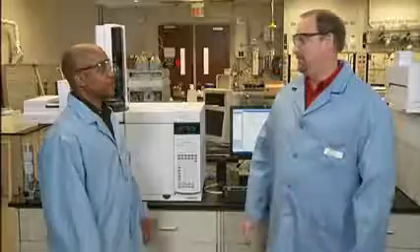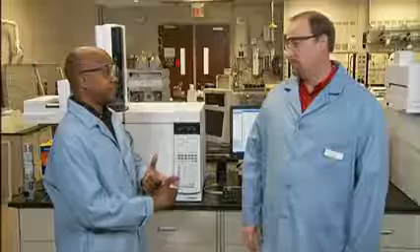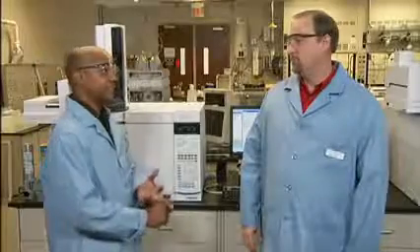So what now? You've eliminated your injector contamination and your column contamination as a possibility. You should think about your detector, especially if the noise is increased slowly over time and not immediately after an injection. This is a sign that your detector is dirty. This is an FID detector. There are many other GC detectors and how to clean each may be a little bit more than what we can cover here. But basically, you're going to replace the detector consumables.